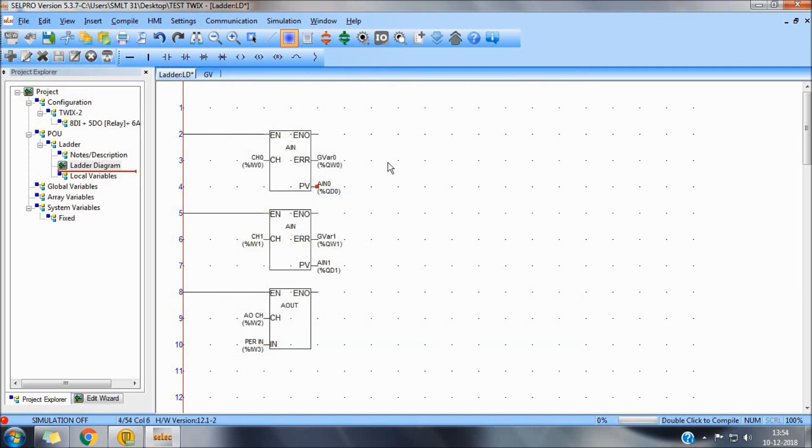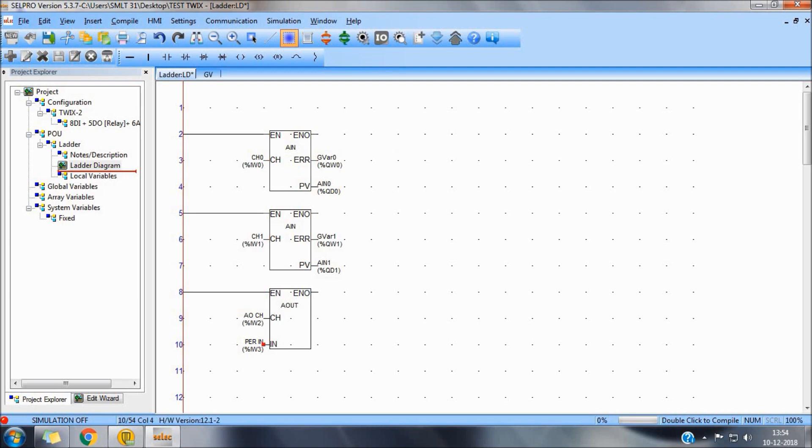Counts at analog input will be 0 to 10,000 for voltage and current. For temperature, it will be actual temperature in terms of 0.1 resolution. For analog output, percentage in, 0 to 1000, which is again 100% in terms of 0.1 resolution. For 0 to 10 volt or 0 to 20mA.